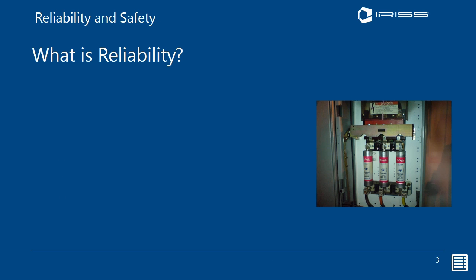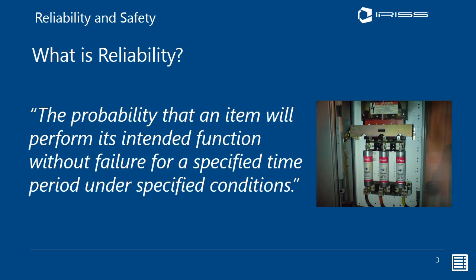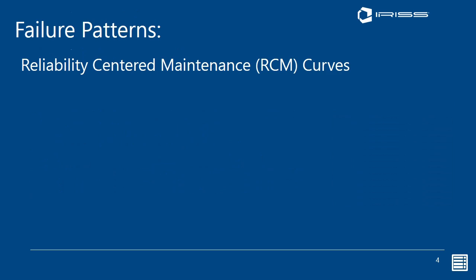What is reliability? Reliability is the probability that an item will perform its intended function without failure for a specified time period under specified conditions. So we need to start to really try and break into what failure means, especially when we're looking at our electrical distribution system. When trying to understand failure, a valuable resource can be found by reviewing the failure patterns detailed in the Reliability Centered Maintenance or RCM curves.